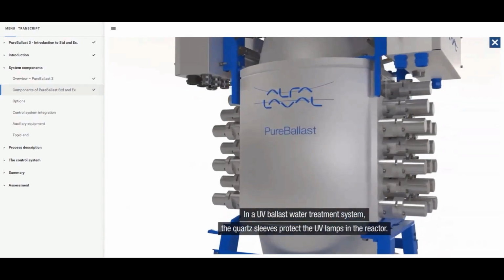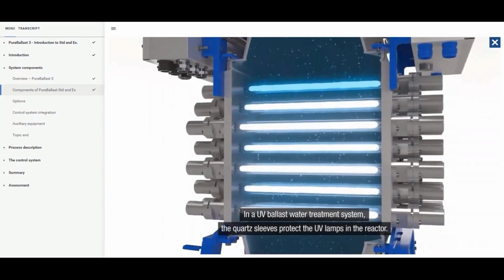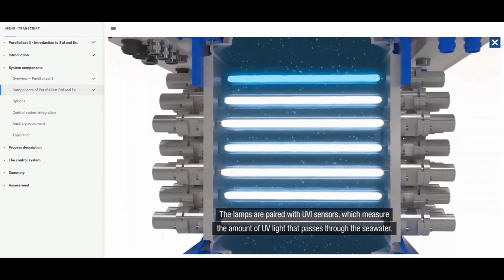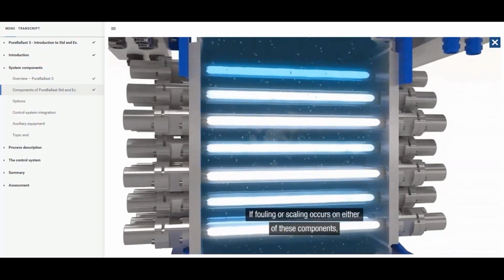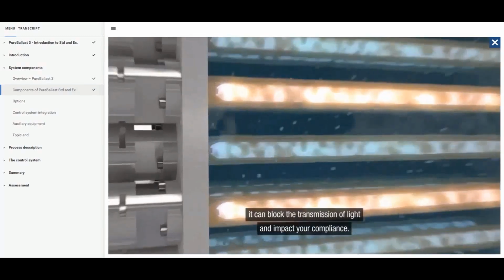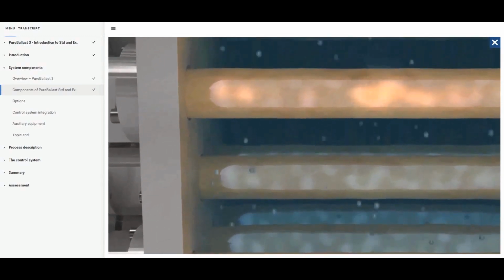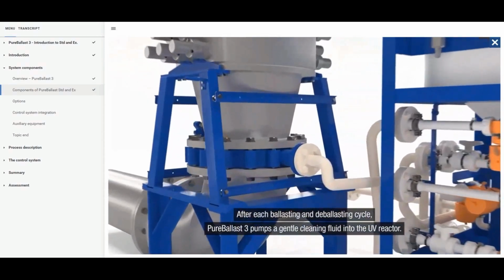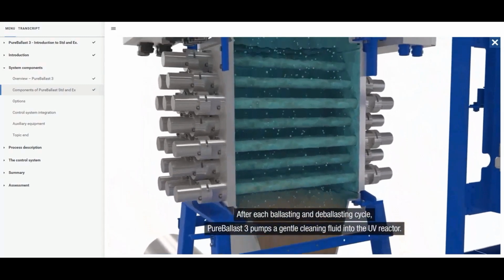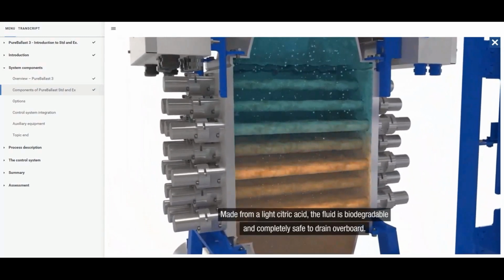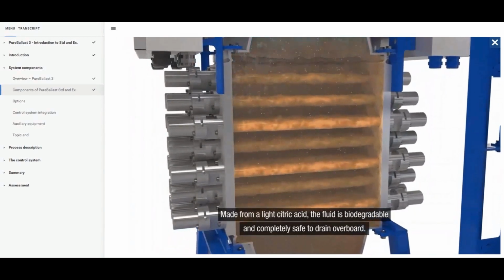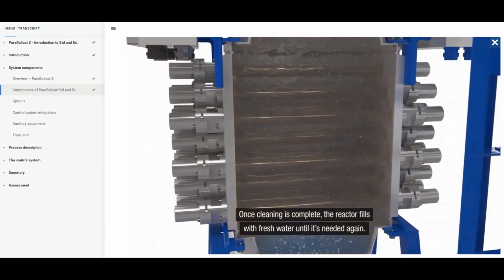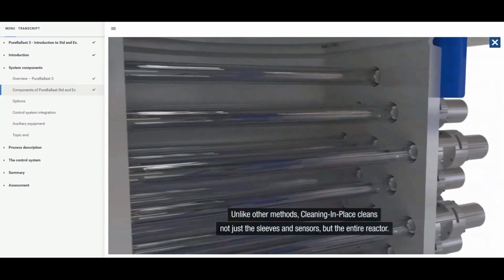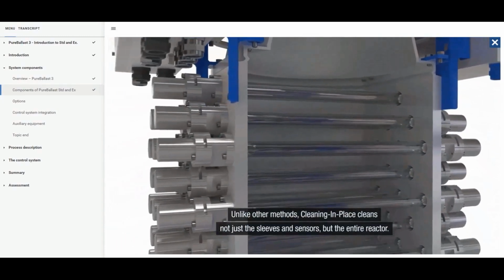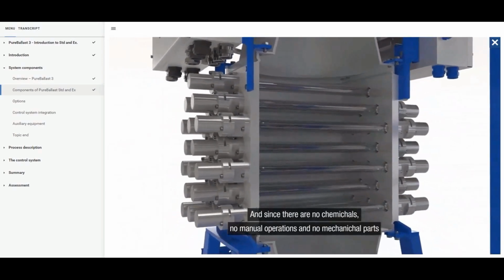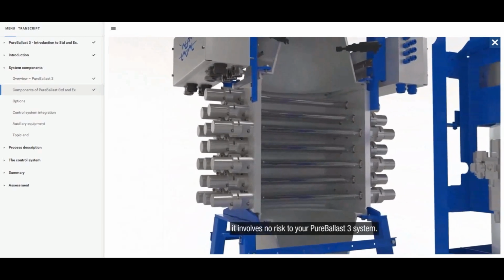In a UV ballast water treatment system, the quartz sleeves protect the UV lamps in the reactor. The lamps are paired with UVI sensors, which measure the amount of UV light that passes through the seawater. If fouling or scaling occurs on either of these components, it can block the transmission of light and impact your compliance. That's where cleaning comes in. After each ballasting and deballasting cycle, Pure Ballast 3 pumps a gentle cleaning fluid into the UV reactor, made from a light citric acid. The fluid is biodegradable and completely safe to drain overboard. Once cleaning is complete, the reactor fills with fresh water until it's needed again. Unlike other methods, cleaning in place cleans not just the sleeves and sensors, but the entire reactor. And, since there are no chemicals, no manual operations, and no mechanical parts, it involves no risk to your Pure Ballast 3 system.